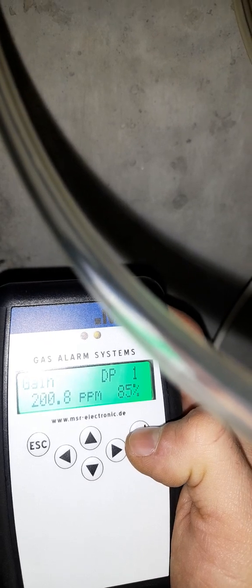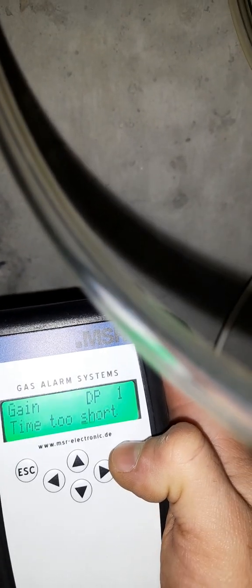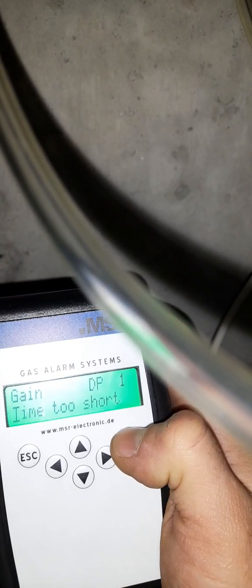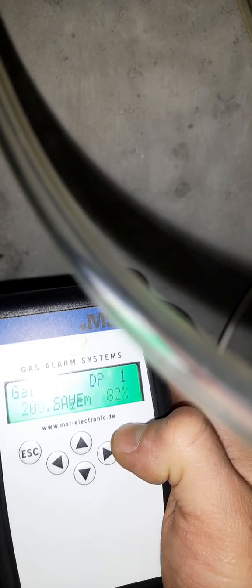Normally you have to calibrate it on 200 ppm. It's at 198, and the health you can see on the right side is 85%, so the sensor is good. Now we're going to press it, time too short, press it again, 10, save. Then we're going to close the bottle. Okay, we have to close the bottle.